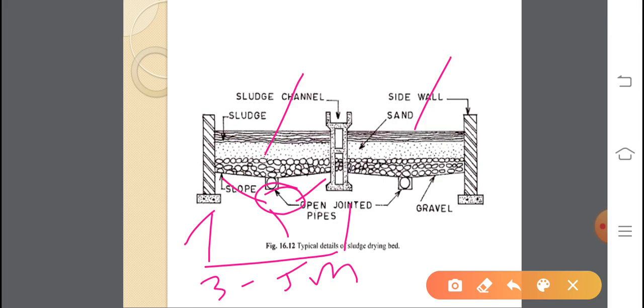The depth accommodates gravel and sand layers. Gravel is provided at the bottom level at 300 mm, and sand is provided at 150 mm. The cover is open to sunlight, so more sunlight means the water in the sludge dries faster through heat.